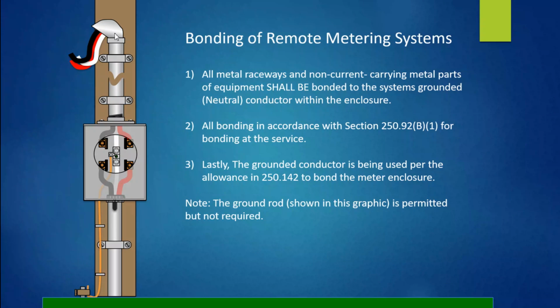So I've got the raceway coming down from the weatherhead. This is the service point up here on the left. I don't show anything of terminations to the utility. I just show the conductors coming out. It comes down the raceway, goes into the hub at the top. Acceptable. We saw this in 250.92(B). And here it bonds to this enclosure, which bonds this hub, which bonds to this raceway, and this hub bonds it to the enclosure, which bonds it through this screw to the grounded conductor.